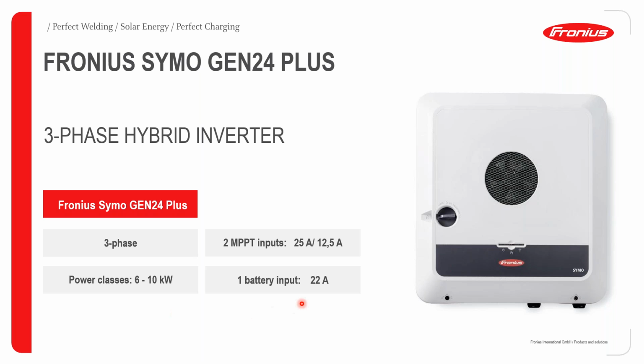And then it has a battery input. So this is now going into battery storage. As my colleague had mentioned before, if you do require battery storage with the Snap INverter series, you, in most cases, will have to do an AC coupled configuration. But with a Gen 24 Plus inverter, you have the possibility to incorporate battery storage through the provided battery input.